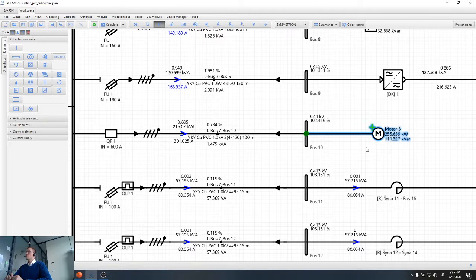These sequences are actually a mathematical thing to calculate unsymmetrical networks. But basically those sequences can also be practically measured in an electrical network. So during unsymmetrical operation of the motor, negative sequence increases greatly, and if there is a negative sequence increase, we can use special relays to disconnect the motor. However, negative sequence relays are not that cheap, and usually they are used only for expensive motors. So for small motors, negative sequence relays are not used.